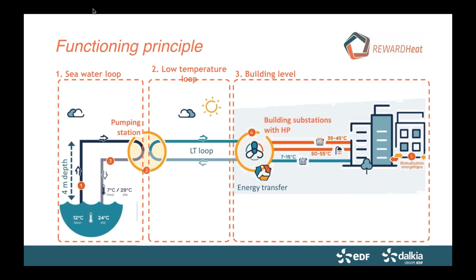So this is the network as we got it. On the left side you have the pumping station, the exchanger station, about 5 megawatts installed capacity. And we have already our first customer, it's pretty interesting, which is the casino - a casino really where you gamble. This one has high cooling needs during the evening, even outside heating or cooling time, so it already exchanges calories into the network and influences all the other customers behind.